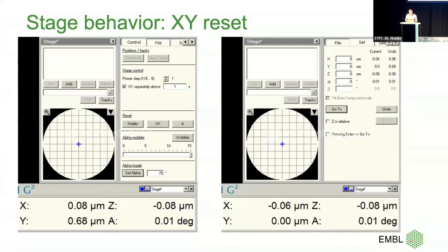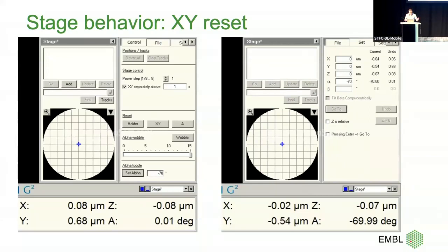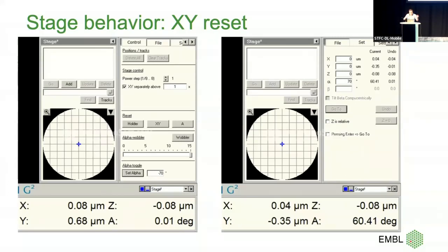I thought: what if we reset X, Y, Z, and alpha back to the original position before we started tilting? That's exactly what the second movie shows — you set positions, tilt somewhere, and once at that tilt the software resets back to original XY positions. By doing that, reproducibility went back to about 200 nanometers with smaller total shifts. FEI Tomo had this since around 2002; I still do it in SerialEM and get smaller shifts. SerialEM has it now and you can switch it on or off.